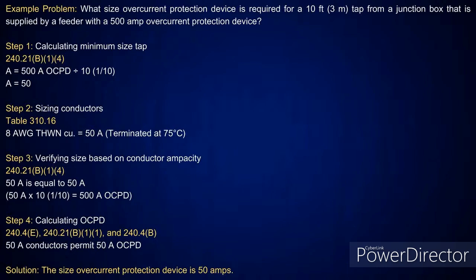Okay? So looking at this, I've got a 500 amp upstream overcurrent device divided by 10 gives me 50 amps. I'm going to terminate this at 75 degrees C, which is a number 8 conductor, which is good for 50 amps. So basically, the very minimum that tap can be is a number 8 rated at 50 amps. And then, of course, you look at Table 240.6(A), the 50 amp matches up with the 50 amp for the conductor size. And therefore, the very minimum that tap can be is a 50 amp overcurrent device with number 8 conductors. Now, let me state this. If I take that tap all the way up and tap off of that at 500 amps, it's no longer a tap at that point. Anything from 50 amps up to that 500 amp is a tap.